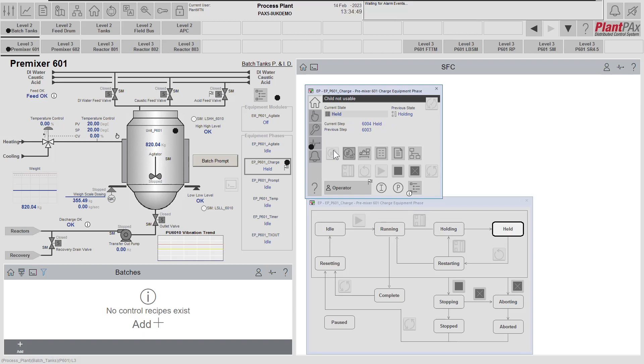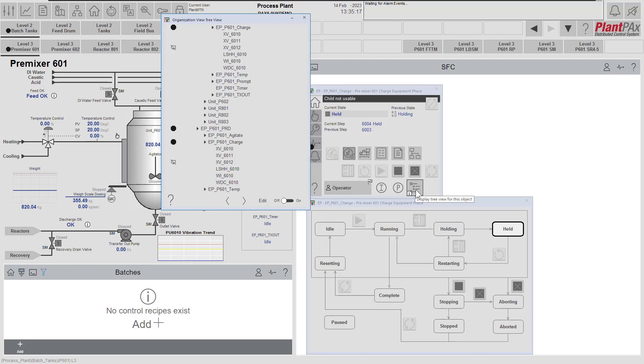Now we can see that there was an issue — the equipment phase was not able to acquire all of its children, and that has caused it to go into the hold state. Because it's gone into hold, it's told the user with a step text. Using the organization ownership and arbitration framework, it's very easy for the user to understand exactly what the issue is. We can bring up the tree view of organization ownership and arbitration, which shows us that the equipment phase is using the following devices.